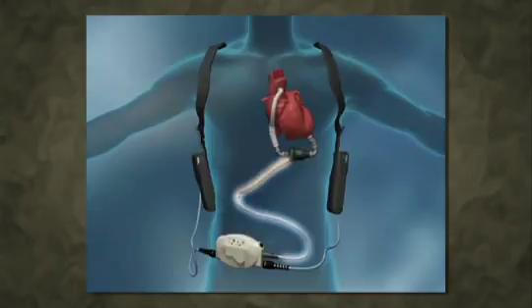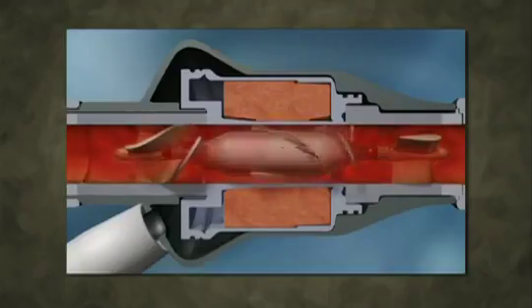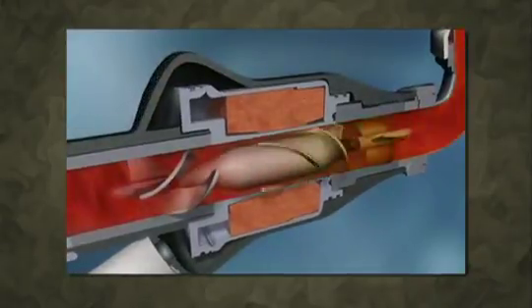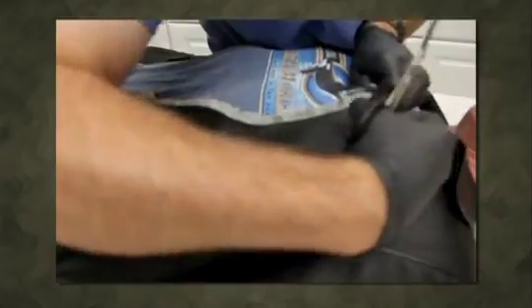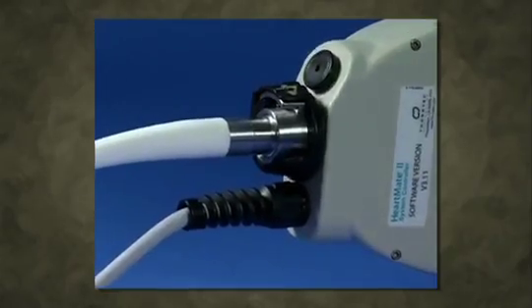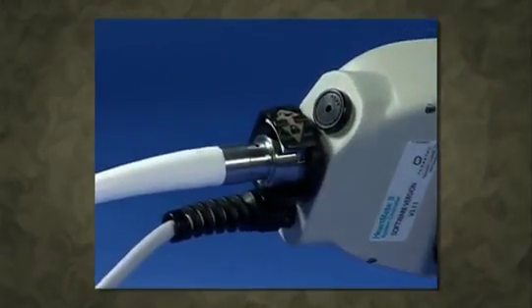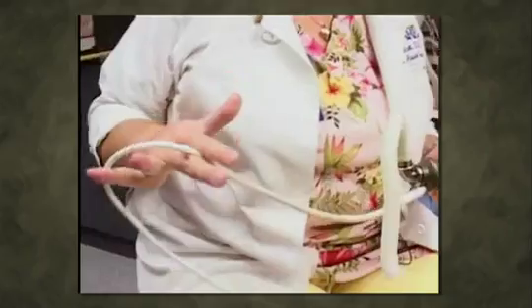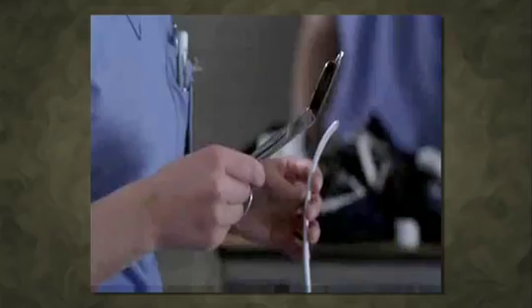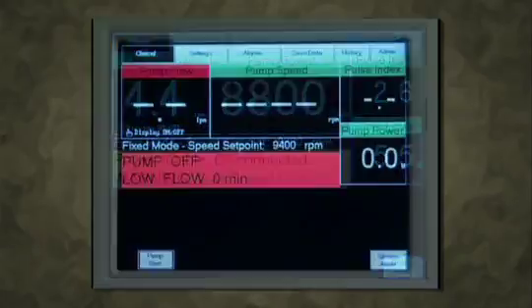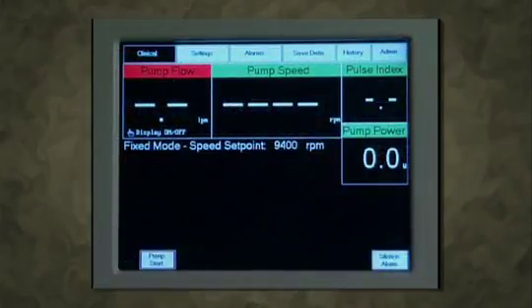This wire provides the power necessary to run the LVAD, as well as the information as to how fast the pump is to rotate. We need to be extremely careful when cutting patients' clothes so as not to sever the wires. We need to also be aware of the system controller. As it is attached to the percutaneous lead, rough handling of it can potentially damage wires or the pump. Dropping the controller could also be an issue. Be aware of the controller and wire locations when moving a patient on a gurney. It goes without saying that severing these wires could be disastrous and could lead to a shutdown of the pump without any way for you to restart it.